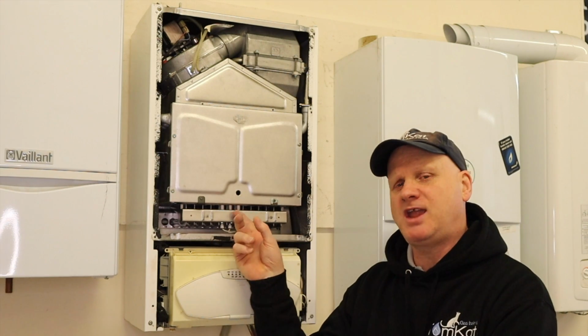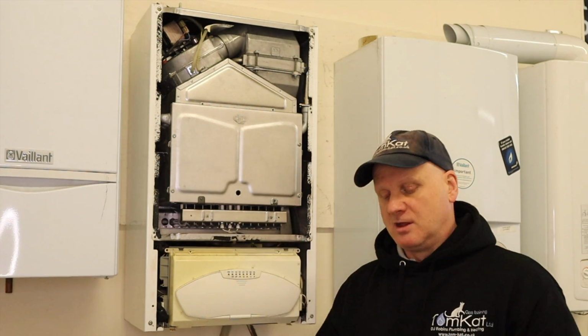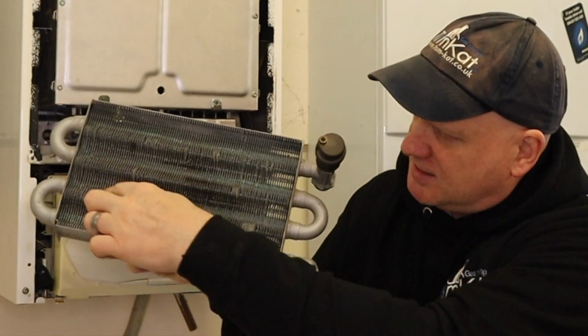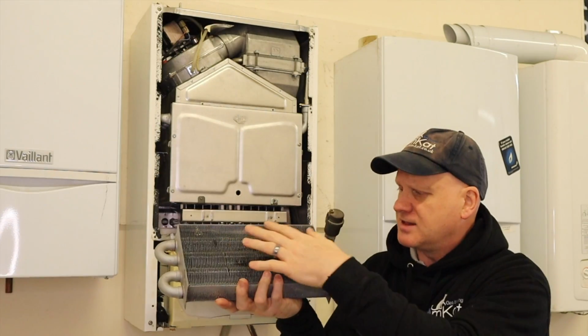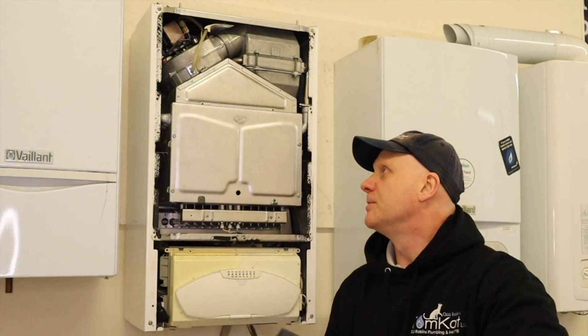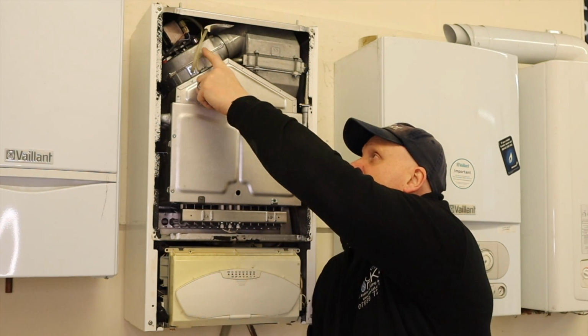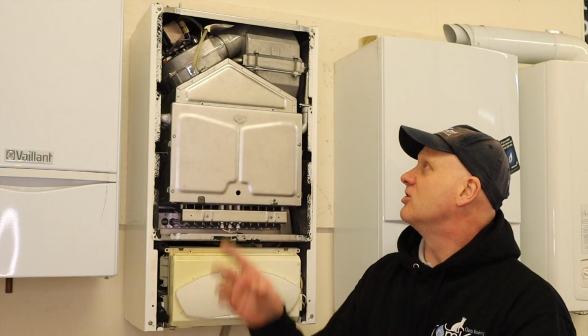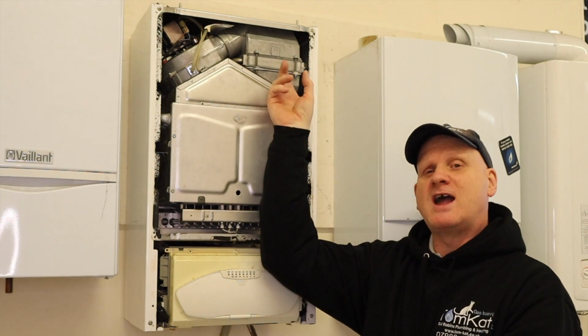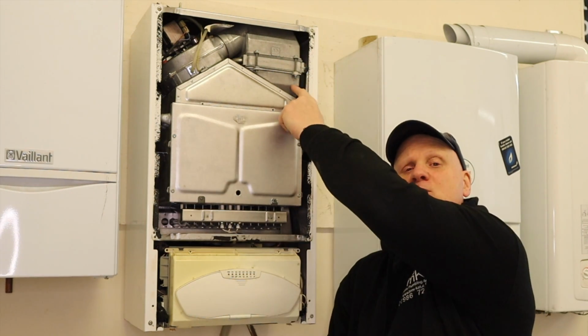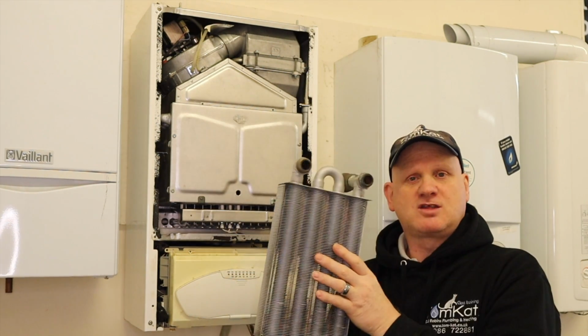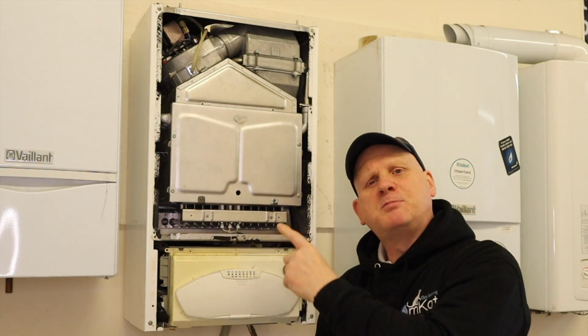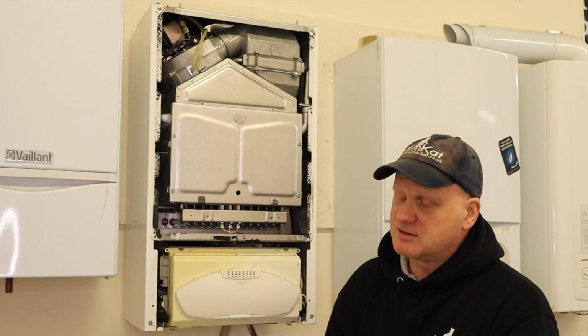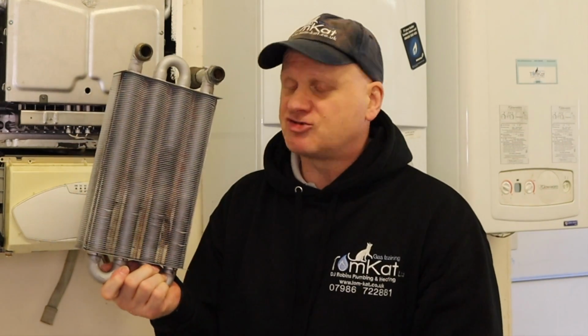So basically this is our burner here. The flue gases go up, the water passes through here. You can kind of see the waterways here. So the water passes through the heat exchanger like that, the flue gases come up, they come into the hood here, and the fan then pushes the flue gases through a secondary heat exchanger, which is made of stainless steel, which is where the condensing process happens. So the return pipe comes into here before it comes back into this copper heat exchanger. So that's how the Band B condensing boiler worked, which there's still quite a few of out there today. So that's copper. Fantastic at heat transfer, but not very good in the condensing process.